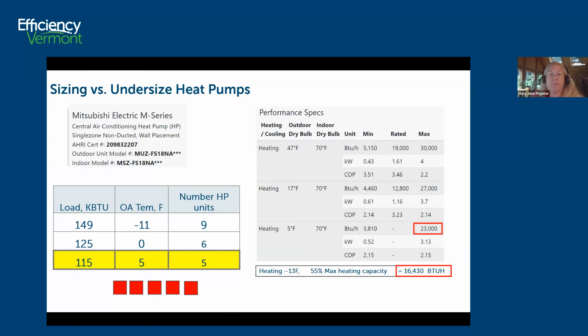On the right is an example of what a heat pump is capable of doing. This Mitsubishi unit is a 30,000. It's rated at 19,000. But look, at 5 degrees, the unit can do 23,000. So this is one of these units that has the ability to do a great amount of heat at a cold temp. So you're going to pay a premium for this type of unit. This will allow you to potentially have fewer heat pumps.